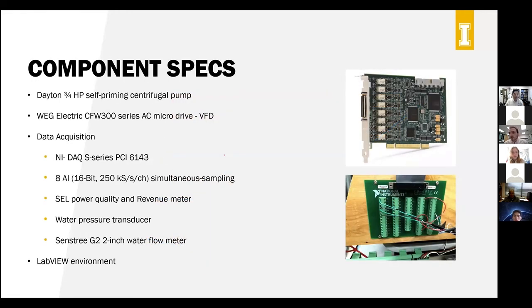So a little more technical specs on what systems and instrumentation we used. We used a Dayton 3/4 horse self-priming centrifugal pump. The VFD is a WEG electric series micro drive VFD. In terms of data acquisition, we used a National Instruments DAQ S series PCI 6143. This system has 8 analog inputs. It runs 16-bit and has 250,000 samples per second per channel of simultaneous sampling. So it allows for a wide range of data acquisition.